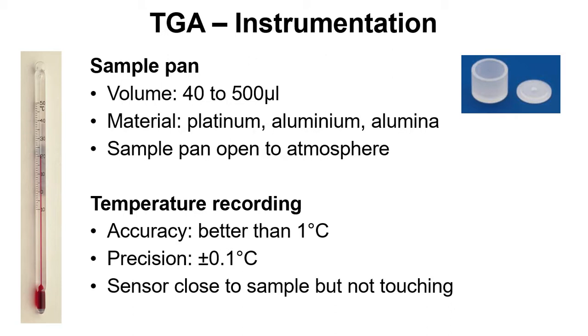The other thing is that if the temperature sensor was actually inside the pan, it could be weighing down on that and could cause problems with measuring the mass changes.